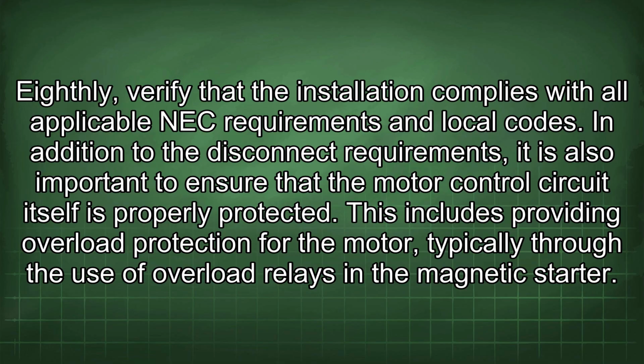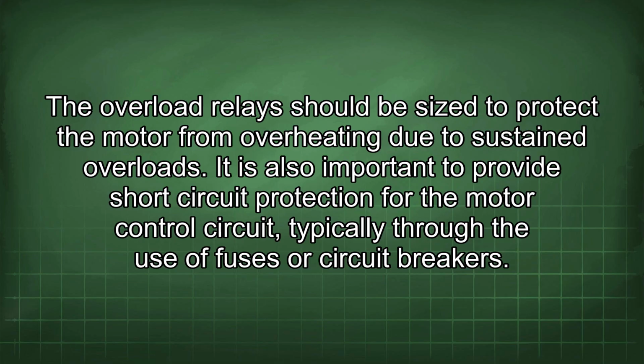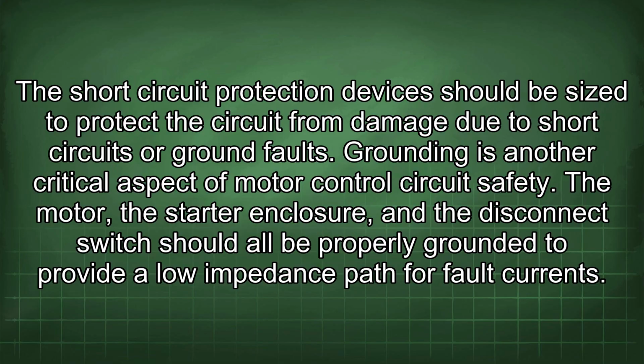In addition to the disconnect requirements, it is also important to ensure that the motor control circuit itself is properly protected. This includes providing overload protection for the motor, typically through the use of overload relays in the magnetic starter. The overload relay should be sized to protect the motor from overheating due to sustained overloads.